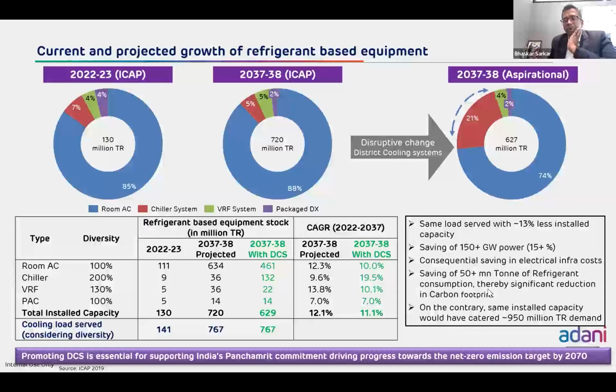And also, if we look at the other way around, if we are increasing to 720, which was the projection, how much of load could we have served? We would have served 950 million TR demand. So this situation is really something which actually provokes us to think why we should not promote or why we should not install district cooling systems all around. So with this, we go to the next.